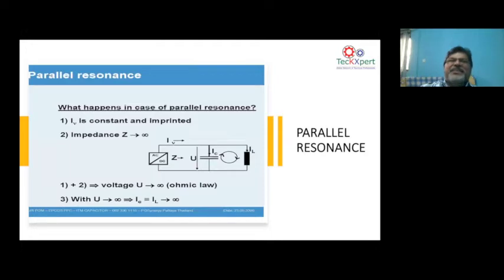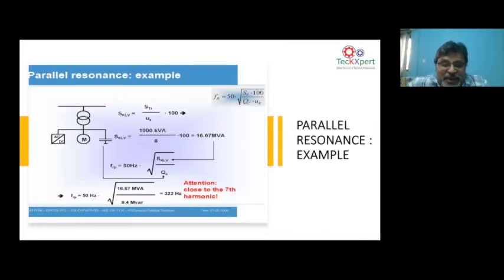So we never will have an infinite impedance or an infinite voltage, because in parallel resonance, even though your capacitive impedance and your inductive impedance become equalized by each other, the resistance of the network will ensure sufficient dampening is done to control the voltage rise or control the parallel resonance. That is what this parallel resonance is showing. Go to the next one.